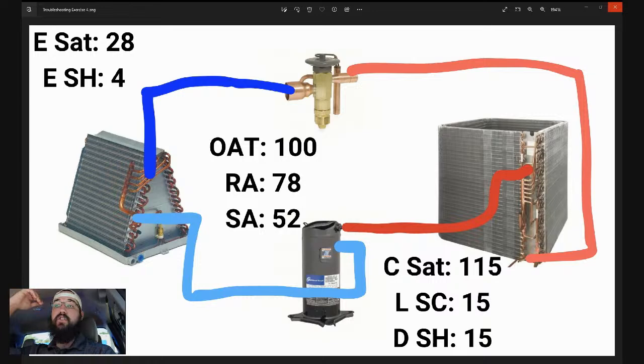Another thing I've done to just get it functioning. So in this particular case, I would have expected to see that our evaporator would have been icing over at 28 degrees. This thing would have taken a few hours to ice over, but a couple of times a day, it would have lost control of the house or the space, and it would not have been able to maintain the load fully. So 28 is enough to do that.